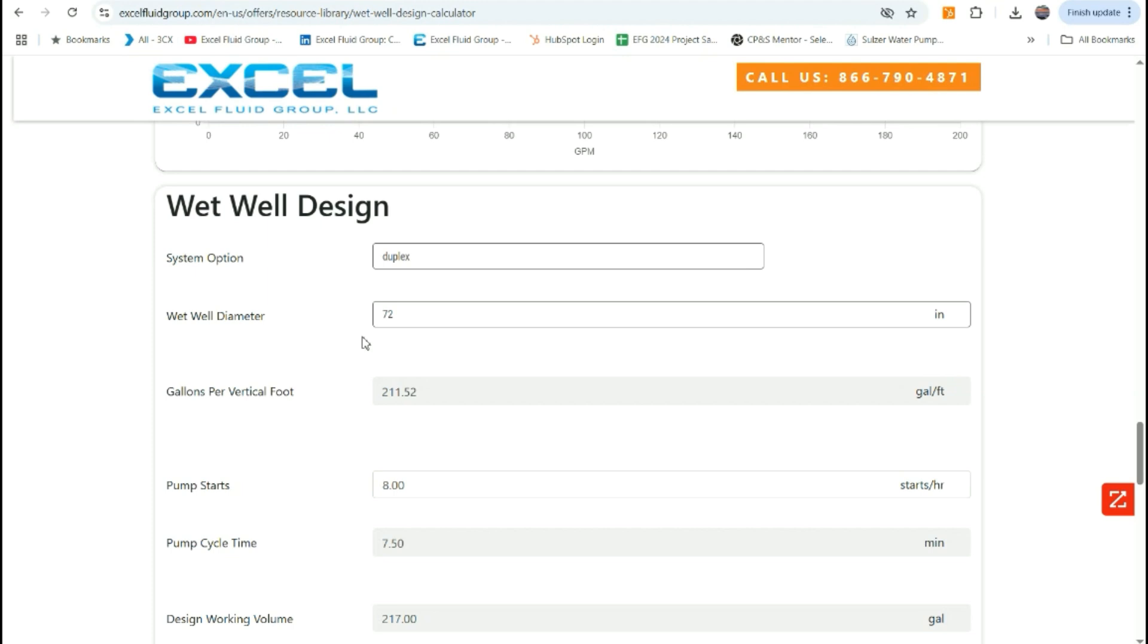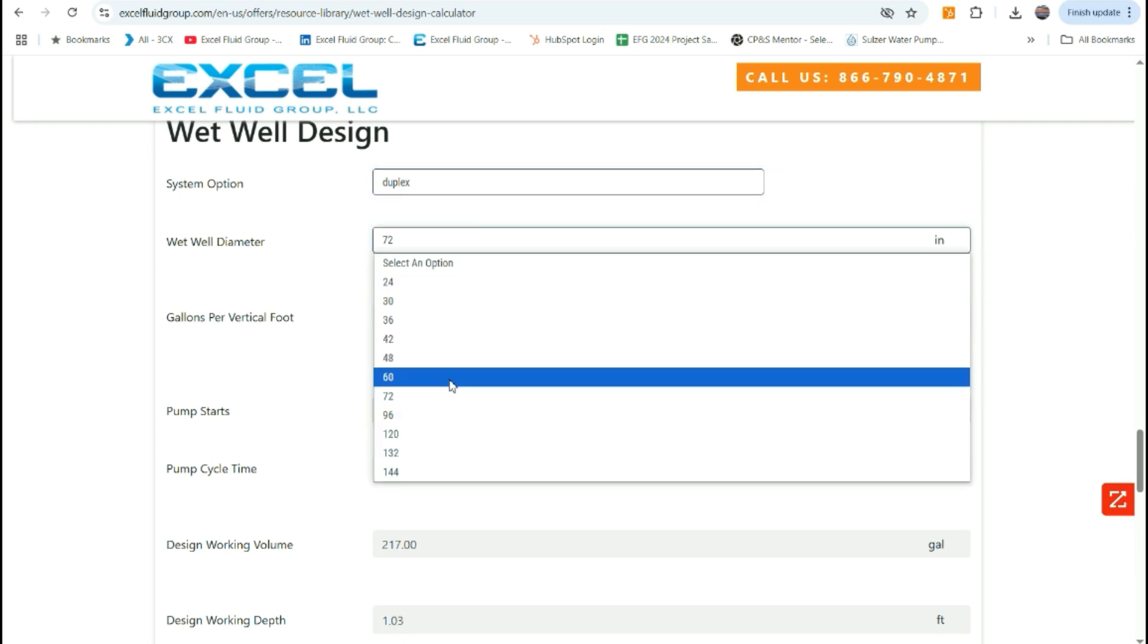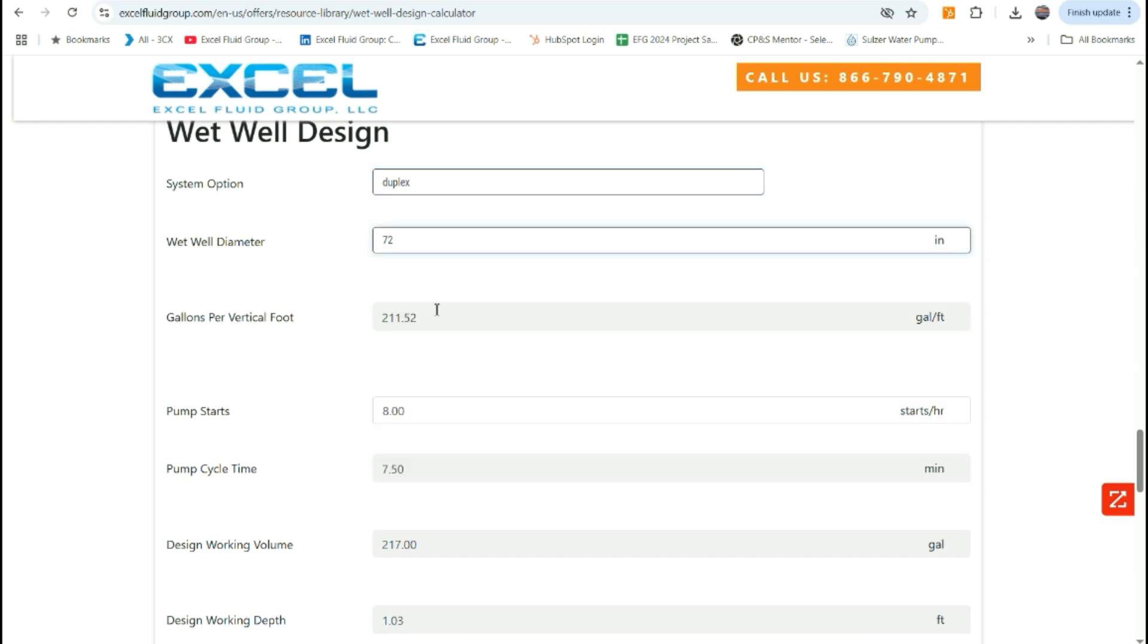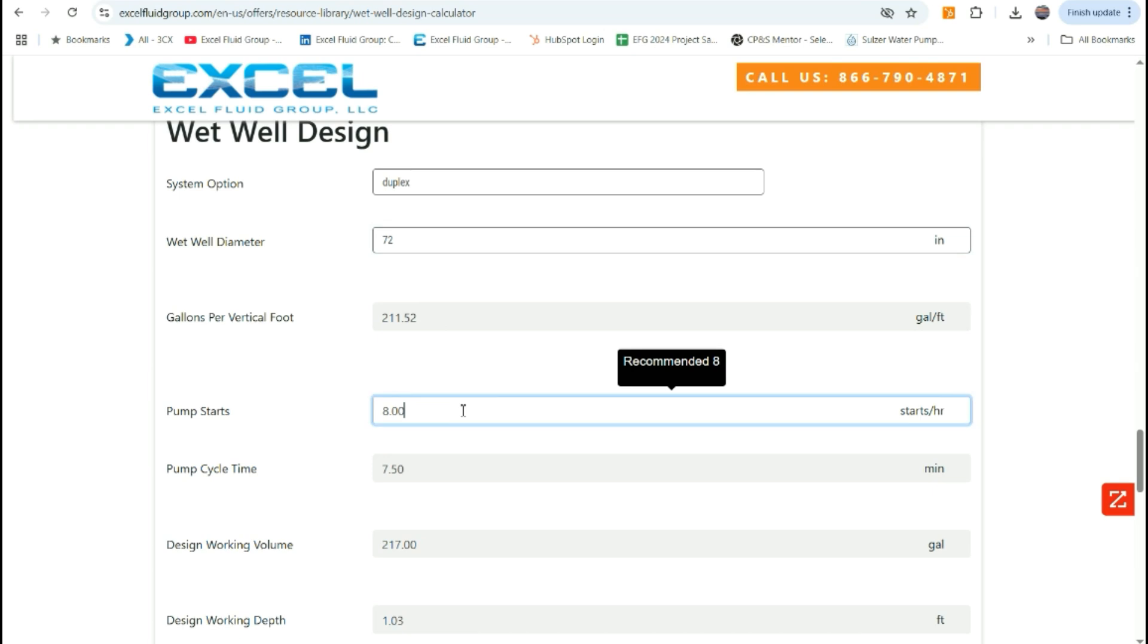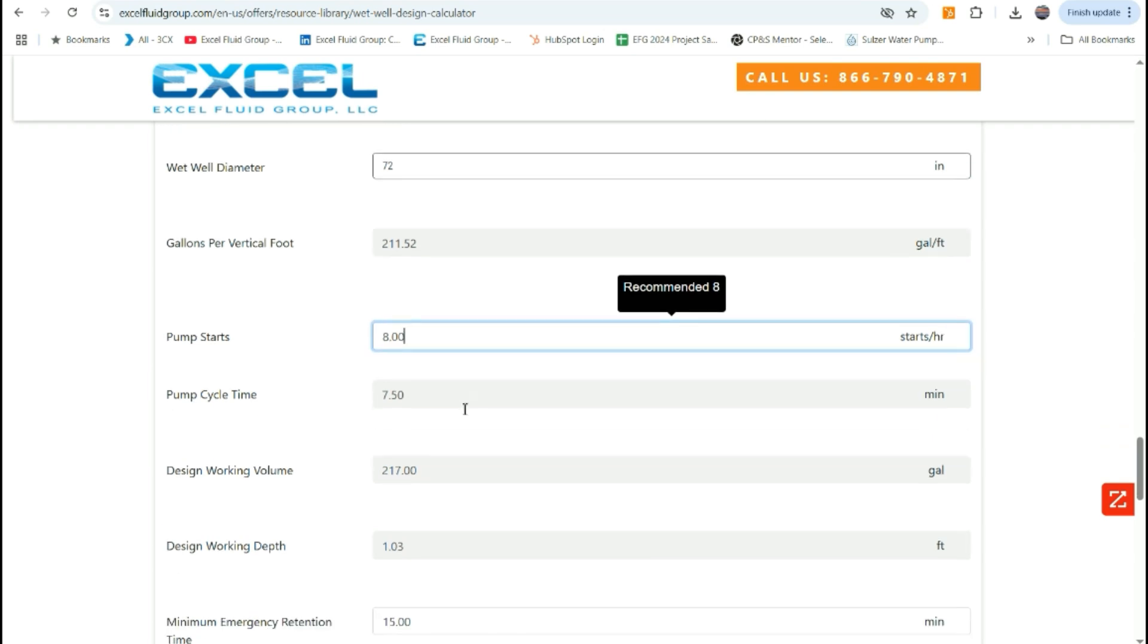On the next section of the design calculator is the wet well design size. Here you can select at the moment a duplex or triplex application. Then you can select your wet well diameter. In this case, we'll select six foot diameter, which shows your gallons per vertical foot. We typically like to see gallons per vertical foot greater than your operating point in gallons per minute. Then you can select your pump starts per hour. The recommendation at the moment is eight. However, this is a user inputted field and typically comes back to the pump manufacturer that you're utilizing to recommend pump starts per hour. Most manufacturers have a maximum start per hour of 15.